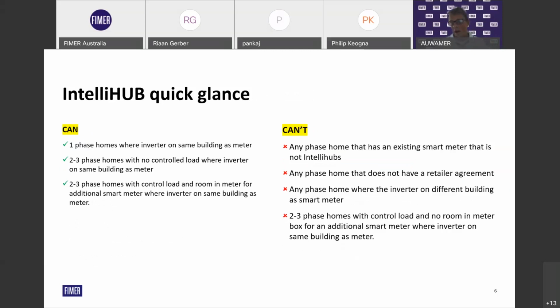Intellihub, at a quick glance, does have restrictions. This is a list of what it can and can't do. What it can do: it's ideal for single phase homes where the inverter is on the same building as the meter, 2 or 3 phase homes with no controlled load where the inverter is on the same building as the meter, or 2 and 3 phase homes with controlled load and room in the meter for an additional smart meter where the inverter is on the same building as the meter. So basically it's restricted to when the inverter is mounted on the same building as the main switchboard where the smart meter is.